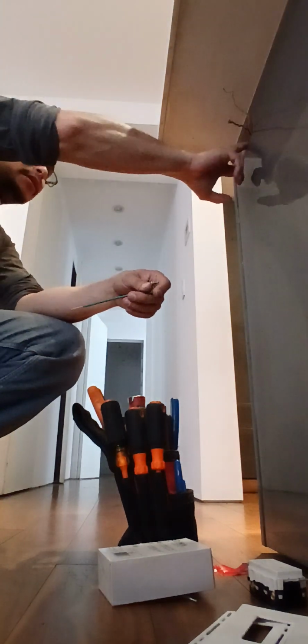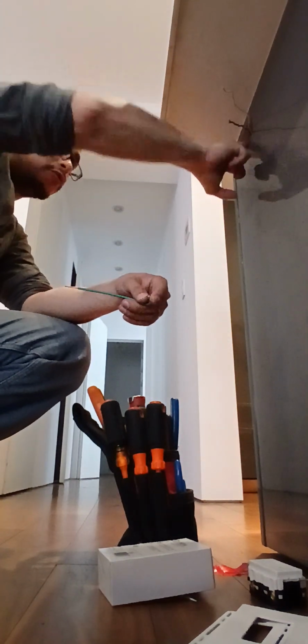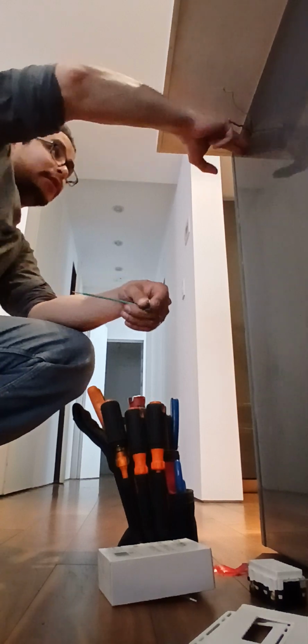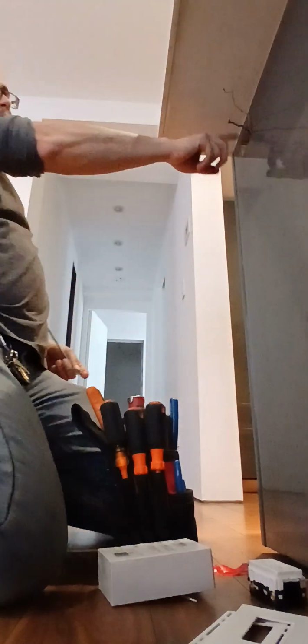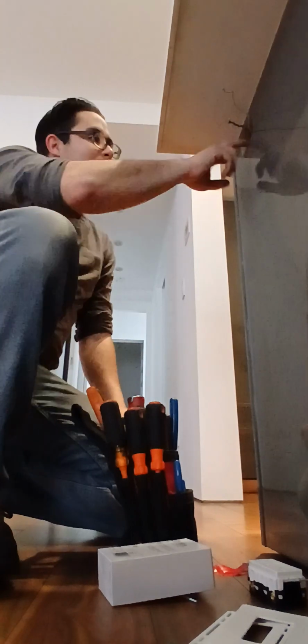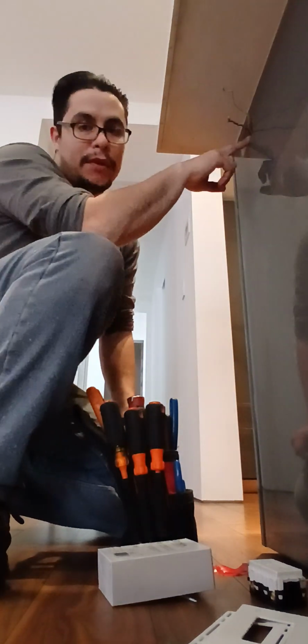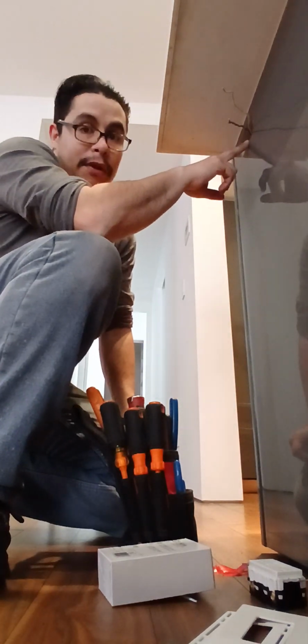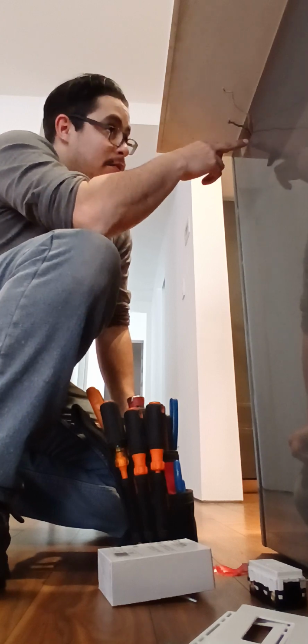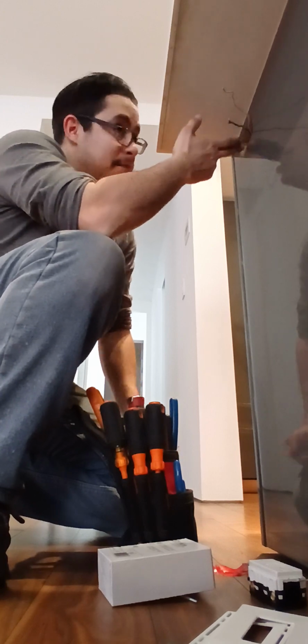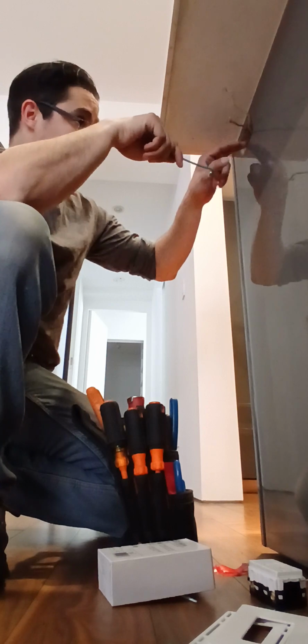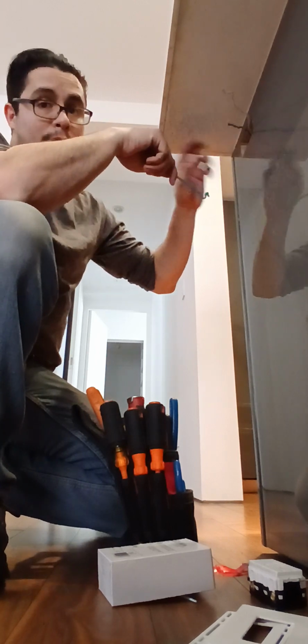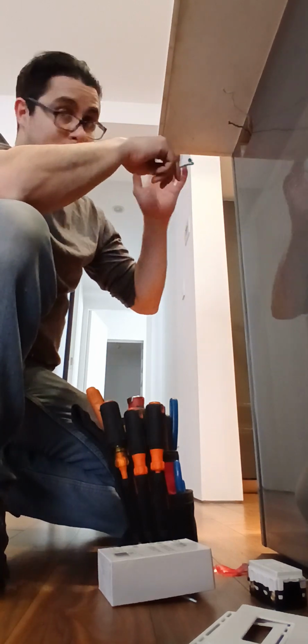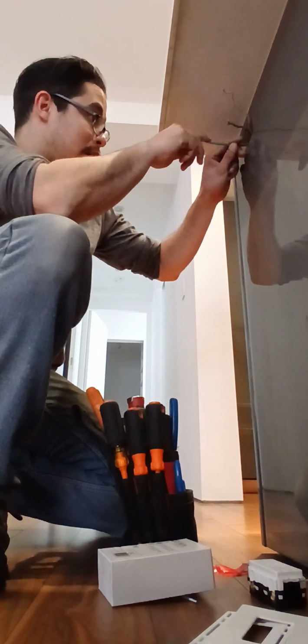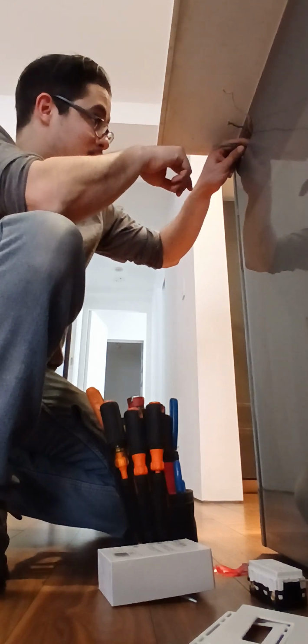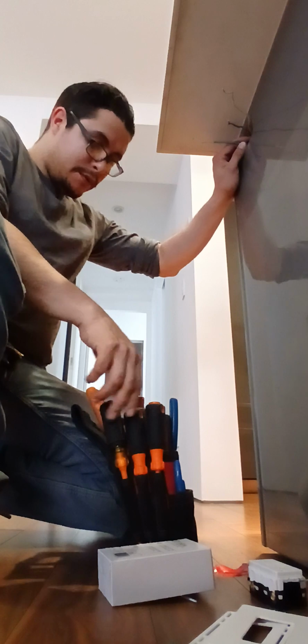But in this instance, this will also need what we call goof rings, but they're called device box extensions, required by New York City code when you have the boxes too deep, more than 1/8 of an inch from the surface of the cabinet or where it's being mounted. You have to cover that gap with that device extension ring, or goof ring, as some of us call it. So it's always good to do that.